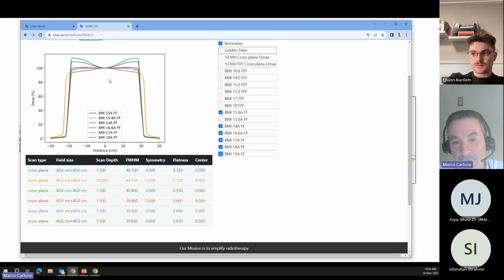And if you look at the actual flatness numbers over here, the 16.6 is a nominal beam. So 16.6 has a very low flatness, but the other beams have higher flatnesses because of the mismatch in energy between the photon beam energy and how the flattening filter was designed.